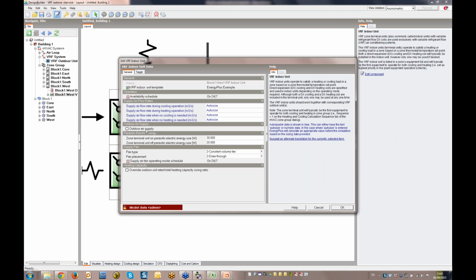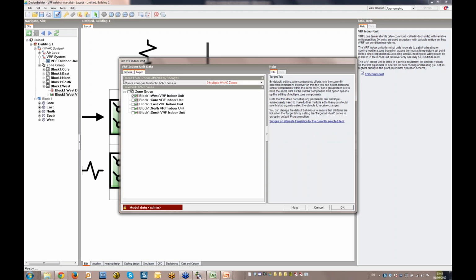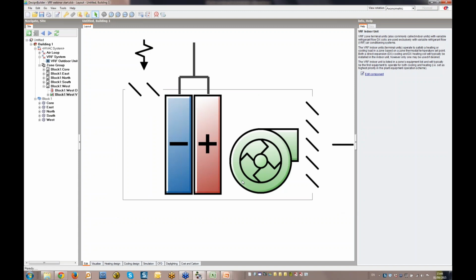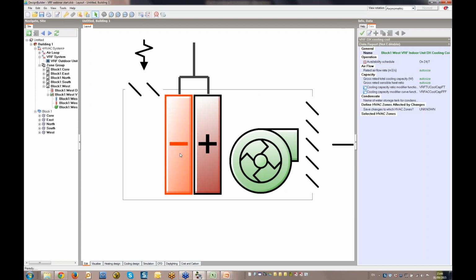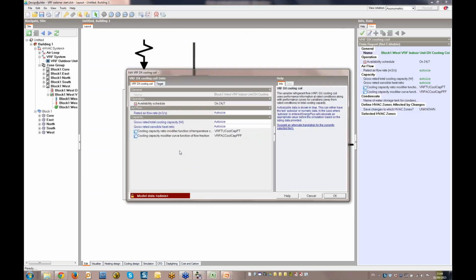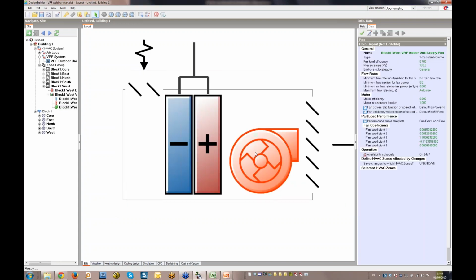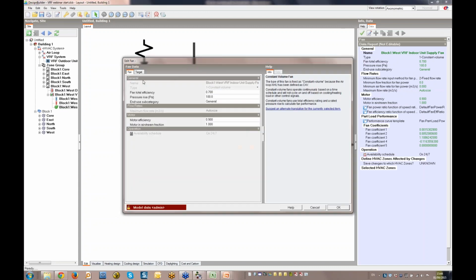Should you need to modify the indoor unit data for specific zones, you can change the parameters, then use the Target tab here to select which zones your changes apply to. The data for the fan and coils in the indoor unit are also editable. Here you can see the options available at coil level and the options available for the indoor unit fans.